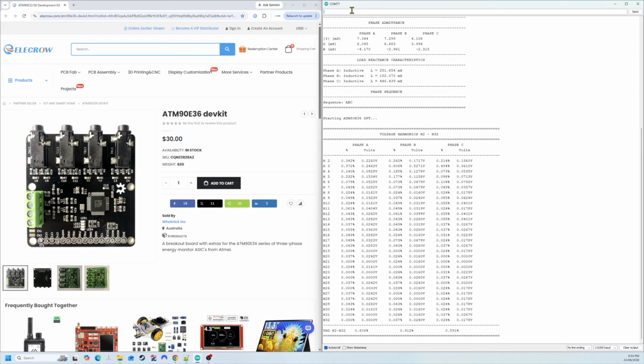Bang. So this reads the harmonics up to the 30th harmonic on the volts. You can see the THD down the bottom for each phase.